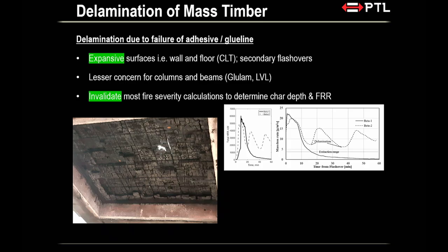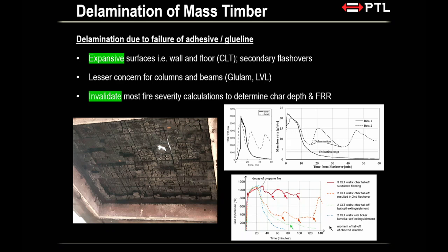And that's a problem, especially if you have firefighters going into the building. They thought the problem is sorted, and then before you know it, the room behind them just flashes over. That's a big concern. It's quite evident on the heat release rate curve, not so much on the time temperature curve, but you can also see its impact.